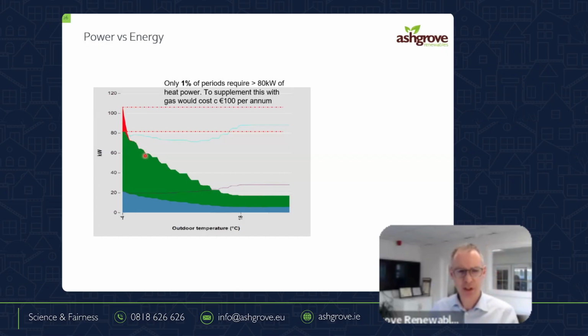For the vast majority of the year, you can see between the bottom dotted line and what the building requires, I actually have plenty of headroom. So my heat pump is way too big. Certainly when I come out here into summer or warmer weather, the heat pump is entirely too big. It's only for a small few days in the year where the heat pump actually now is too small. And the software tells us that in this case, the red little bit there that's sticking out, the heat pump can't cater on that day.